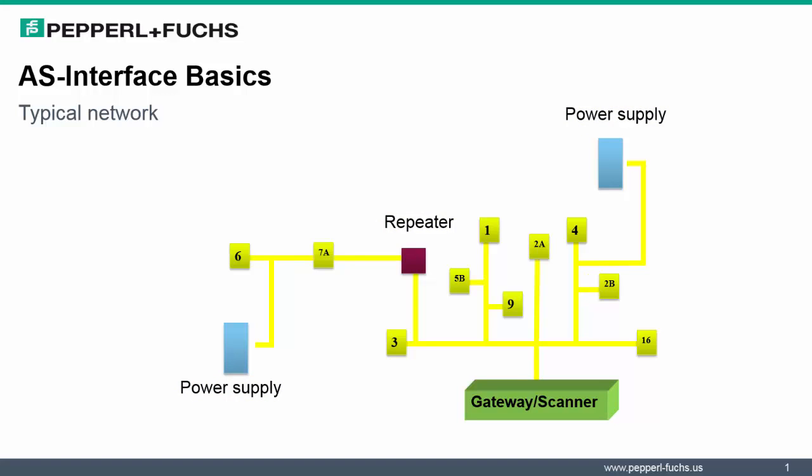The A after each of those addresses are half-addressable, versus the full numbers associated to full-addressable modules. The flexibility in the topology is immediately evident from the diagram. A repeater is used on this network to extend the network beyond the limited 100-meter segment.